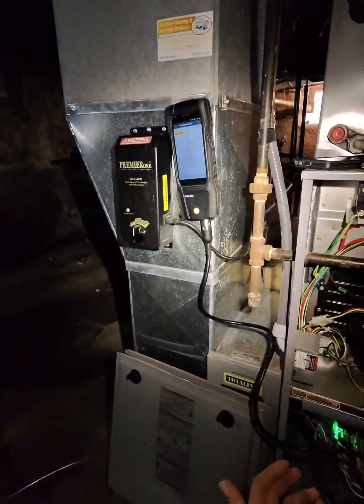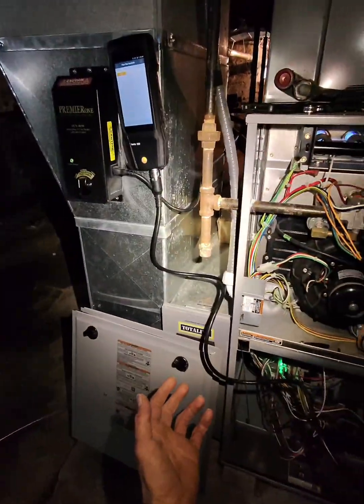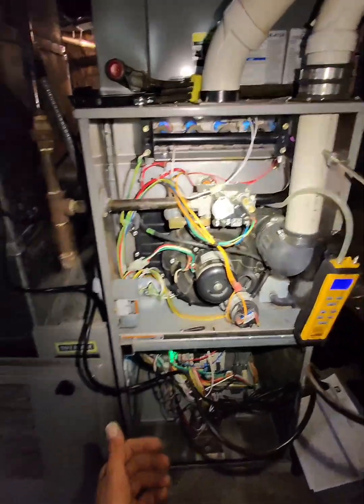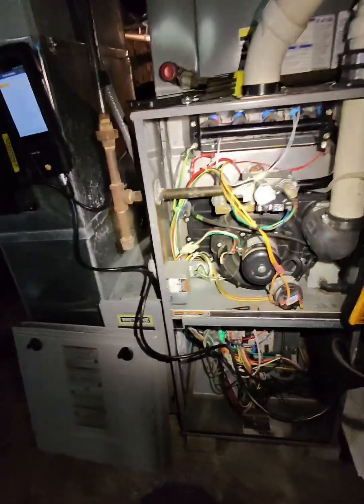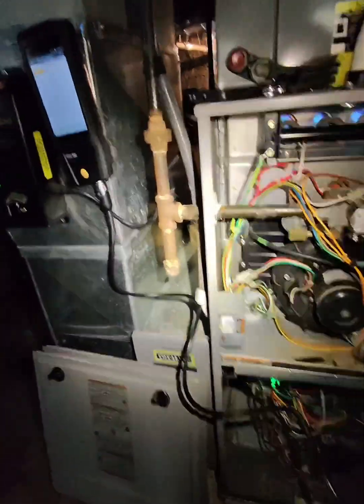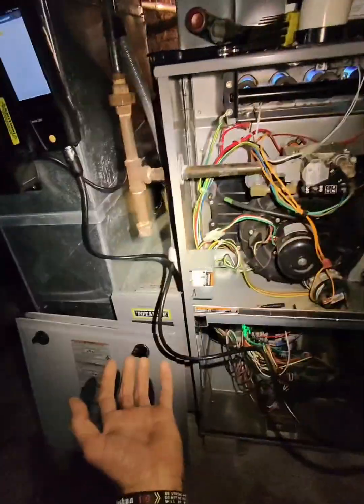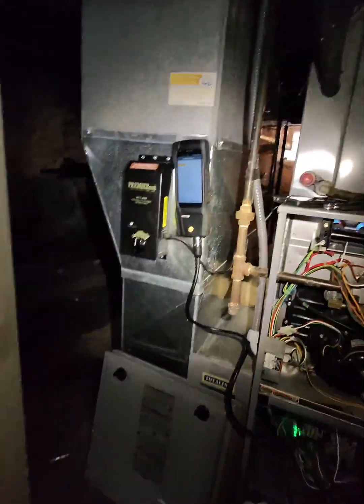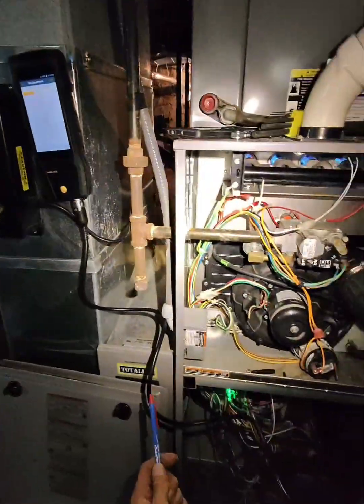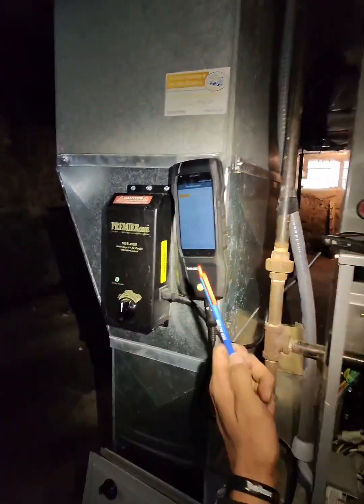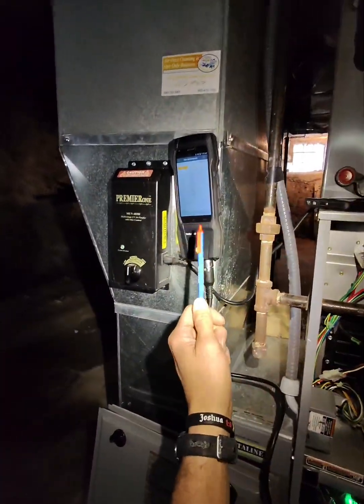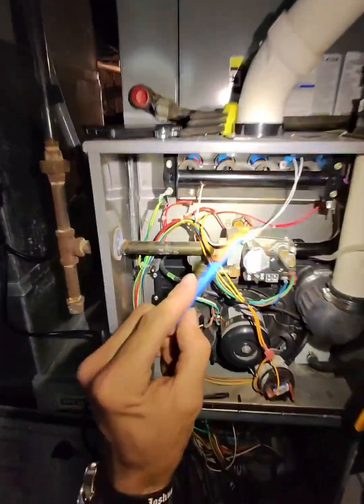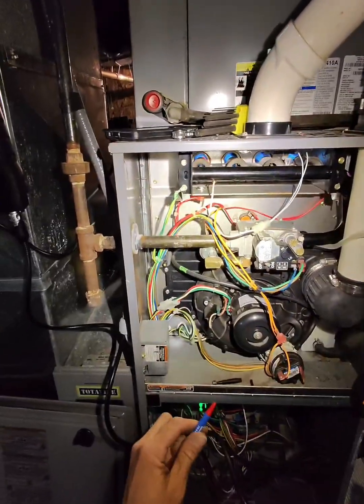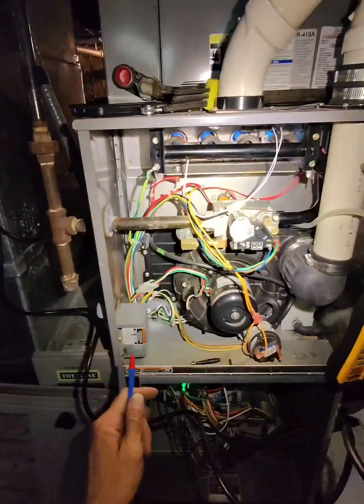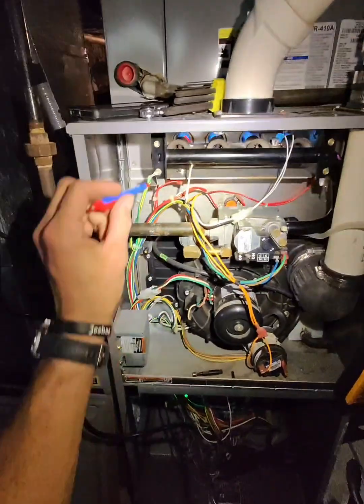But what we have been finding, what my company and I have been finding, is that with propane furnaces, these heat exchangers will go bad sometimes within 7 or 8 years. This one has made it 14 years, but this is a problem with the heat exchanger right here. I did take the burners off and look down there and saw a lot of rust and corrosion. Propane is just eating away at the metal. You can see the screw right in there is hugely corroded.